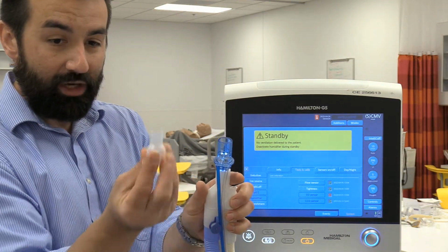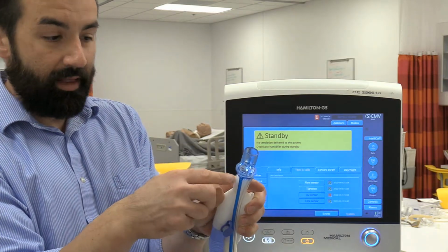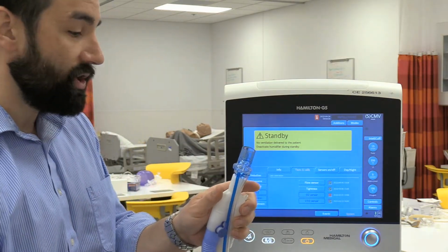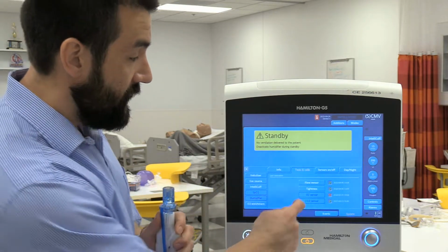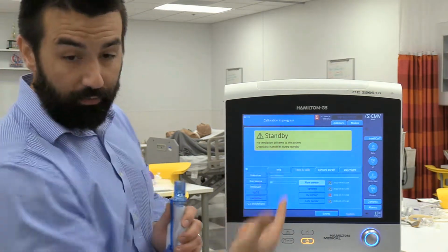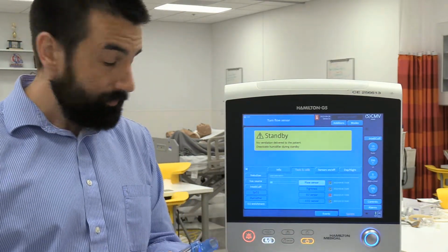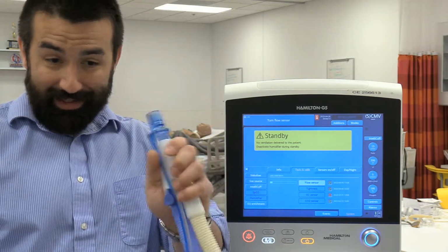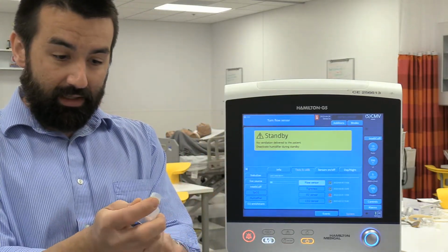And since we don't have a patient, we need something to allow us to hook inside of that 15 millimeter ID connection right here, and that's going to be this. So I'm going to check the flow sensor. It's going to walk us through, so it's calibration in progress here. Turn flow sensor. It doesn't mean go like this.